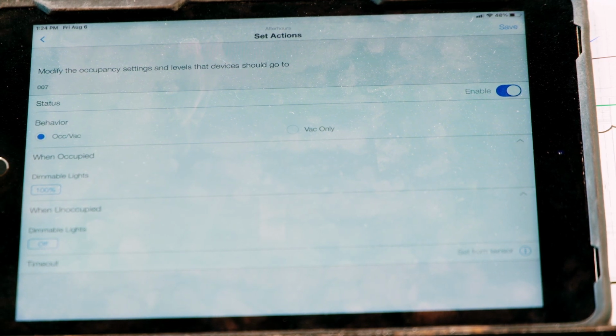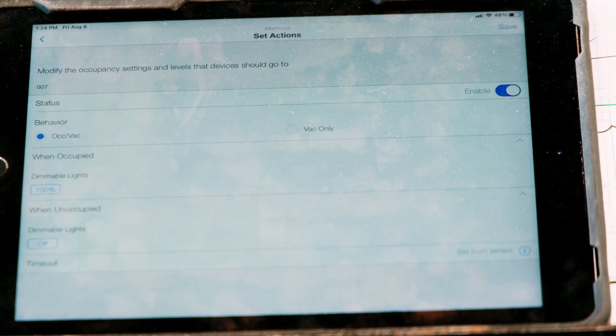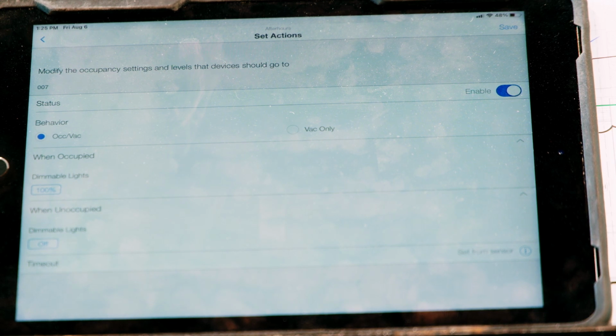And sometimes we get calls saying our occupancy sensors don't work. It's because they're still in that state. So that can happen in areas, especially common areas where you have both controls. We have some walkway, the hallways upstairs have Pico controllers. It could happen there as well. Right? A good thing for that not to happen is maybe make the occupancy time shorter in areas where you don't want to have that happen too much, right?